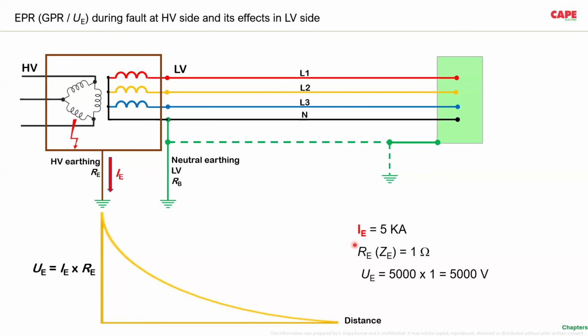Example, imagine the fault current is 5 kiloampere, the current going to the earth electrode. Of course, in no condition will a 5 kiloampere current flow through the earth electrode. This is very, very rare, but just for your information, imagine 5 kiloampere current goes through the earth electrode. Imagine the impedance of the earth electrode is 1 ohm. The UE, meaning the touch voltage or the gradient or the EPR, earth potential rise, at that particular point is almost equal to 5 kV, 5000 volt.